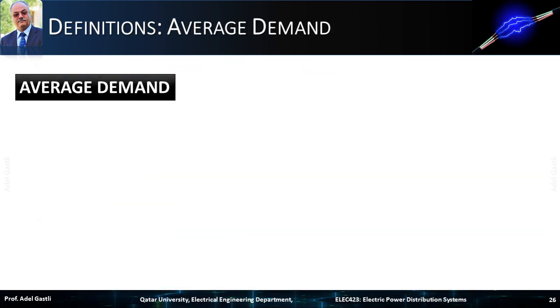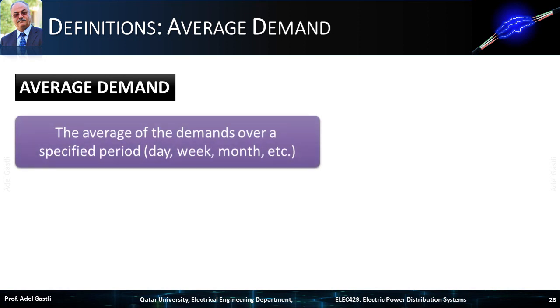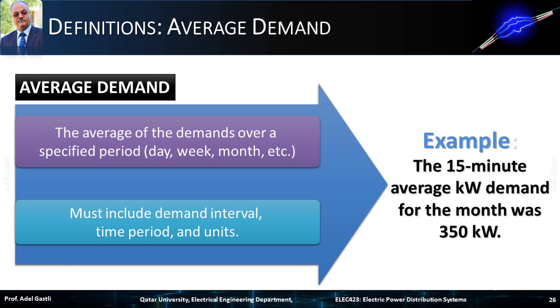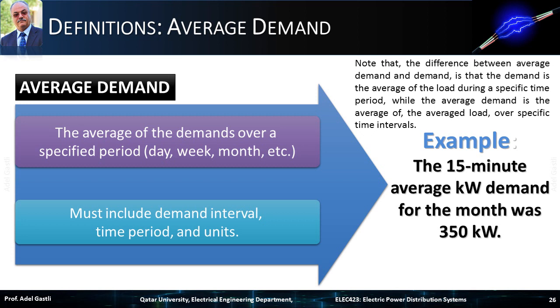Now let's define average demand, which is the average of the demands over a specified period that could be day, week, month, etc. Similarly, it must include demand interval, time period, and units. For example, the 15-minute average kilowatt demand for the month was 350 kilowatts. Note that the difference between average demand and demand is that demand is the average of the load during a specific time period, while average demand is the average of the averaged load over specific time intervals.